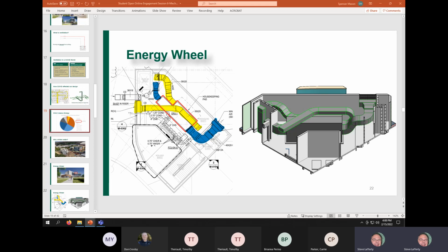It's got two fans in it: one pulls outside air through - that's the blue duct - goes through the unit and down into the building. Exhaust is the opposite: it comes out of the building, through the unit, back over the top, and out. That relates to what happens to the exhaust air. You'll notice it's not a coincidence that the outside air and exhaust air are on opposite sides of the penthouse - that's on purpose, for that reason.